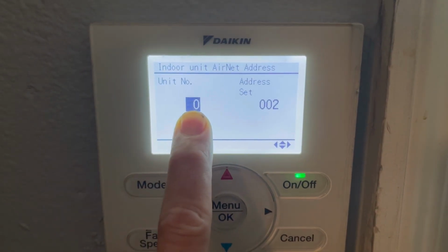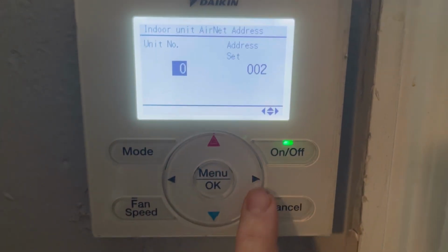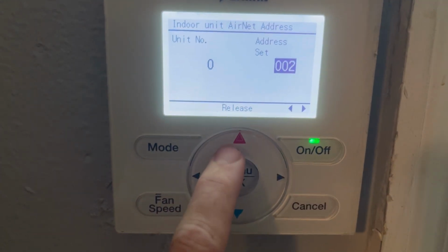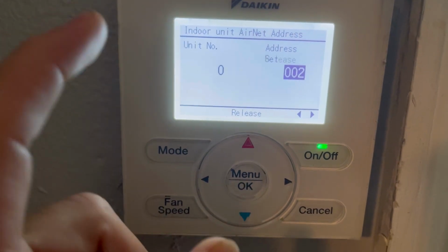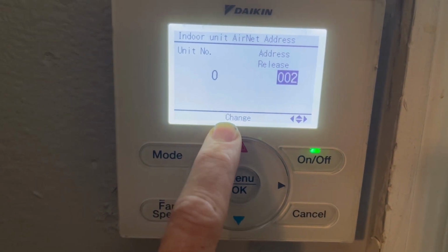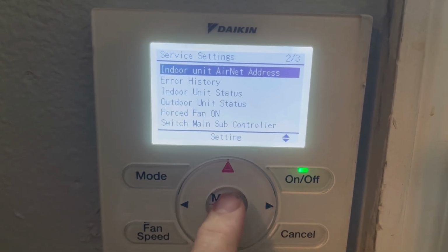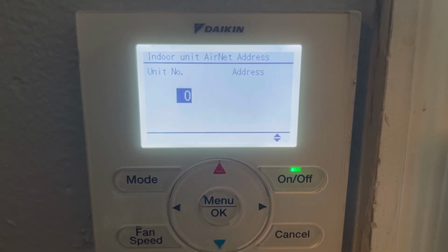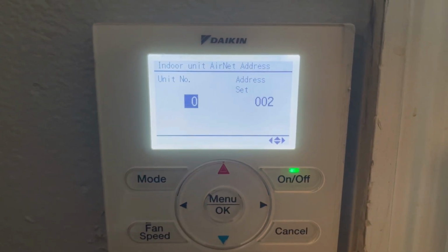Right now I only have one, which is why this number doesn't change. Now if I want to change the AirNet address, I hit right, and I can hit up or down. After I release it, press the middle button to release it. See here, release and change it. Okay, now it's saved. I always tell people to cancel, go out, go back in if you want to see it again. Yes, confirmed. AirNet address is 2.